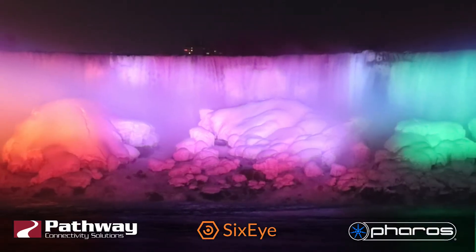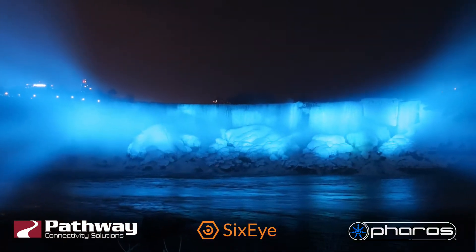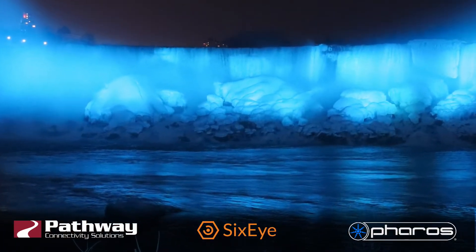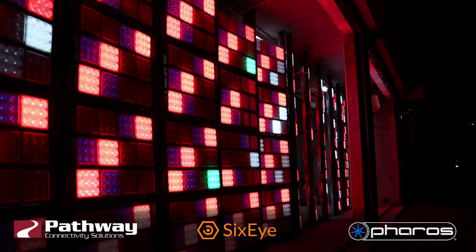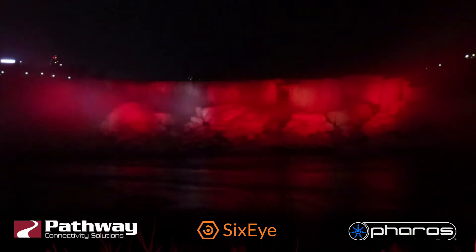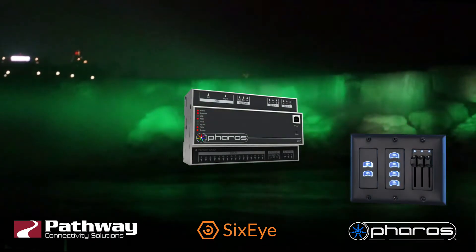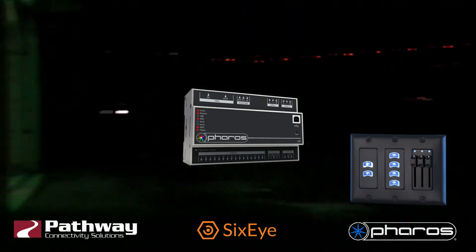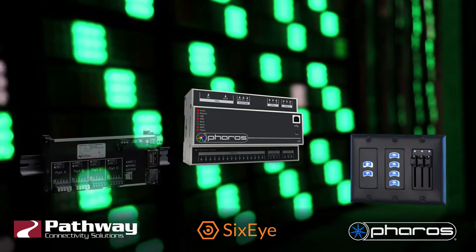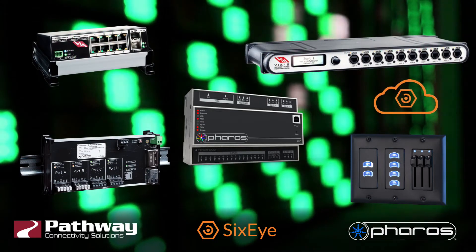In 2017 the Niagara Falls Illumination Board hired a consortium of companies to install a four million dollar LED lighting makeover. We now have RGBW control of all three waterfalls thanks to 1,400 individual luminaires positioned at three different locations on the Canadian side. A Pharos LPC is the main controller with three Pathway Vignette systems providing local backup to the three individual lighting positions. All of that plus a network of Path Ports and Via switches are connected to the SixEye cloud for remote monitoring and management.